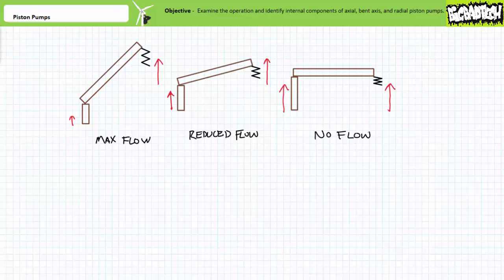Finally, when the piston exerts equal force as the spring, the swash plate is no longer held at an angle and there exists no volume differential. Displacement per revolution is zero and flow stops. In summary: maximum angle, maximum flow; less angle, less flow; no angle, no flow. Simply by varying the angle of the swash plate, a variable displacement piston pump can vary the displacement per revolution and directly control flow rate.